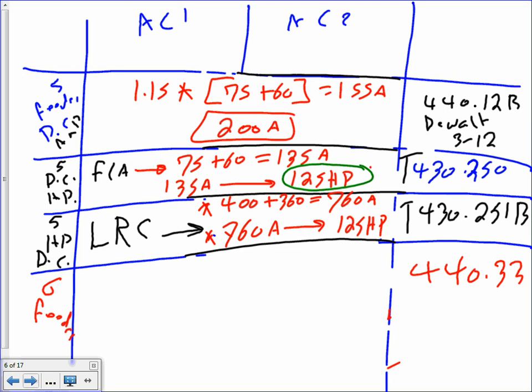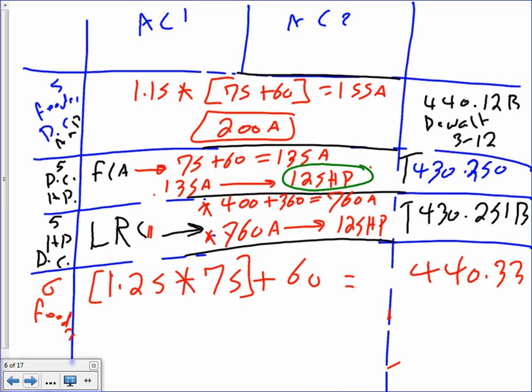The last thing, my friend, always remember, we're dealing with what? HVAC equipment, chillers, rooftop units, compressors, right? All right, so last thing is number six, guys. Number six is a feeder. I've done it before many times. For the feeder, you take the largest motor, 1.25, and multiply this by 75 plus 60. Remember, the brackets are here.